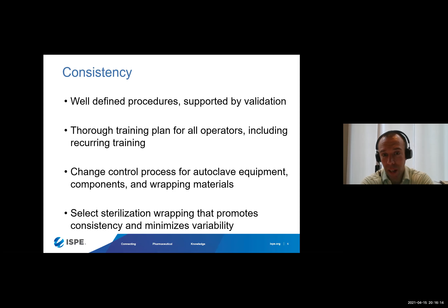Really, this is a holistic process. When we're establishing our wrapping procedures, the process has to include evaluation of different wrapping materials such that these materials promote consistency and minimize variability. So that's part of the change control process. If we have a process or procedures for preparing equipment for sterilization, it's under change control. If anything is altered in the wrapping materials or that process, it could impact the validation, could impact the variability of that process.